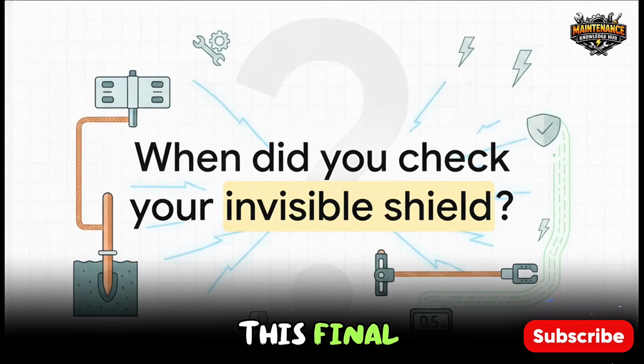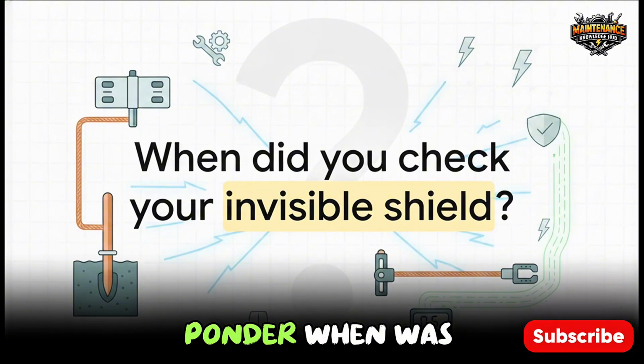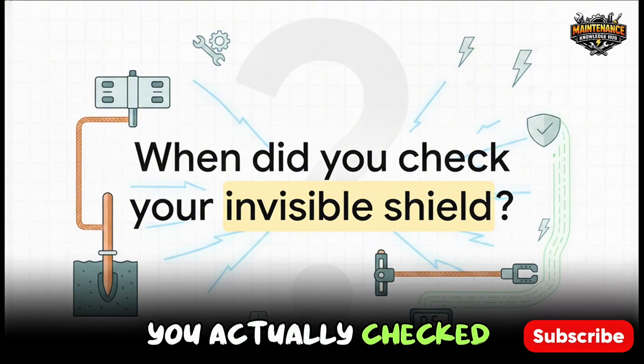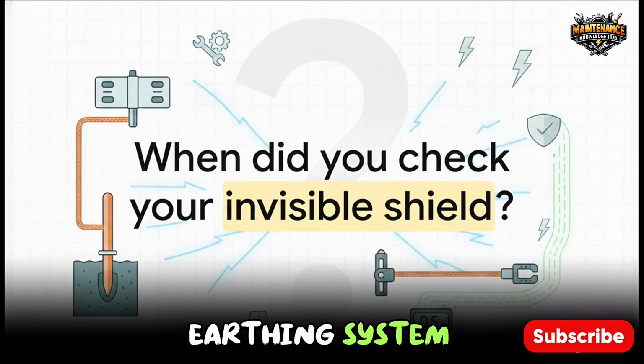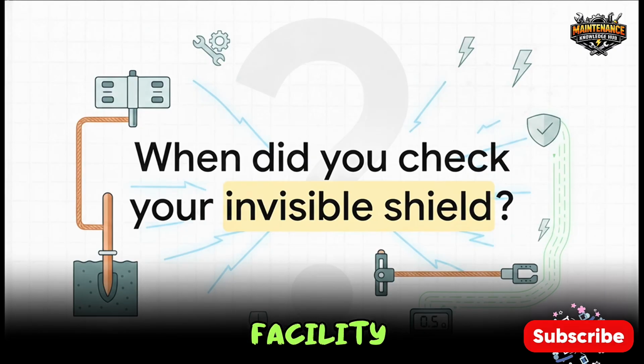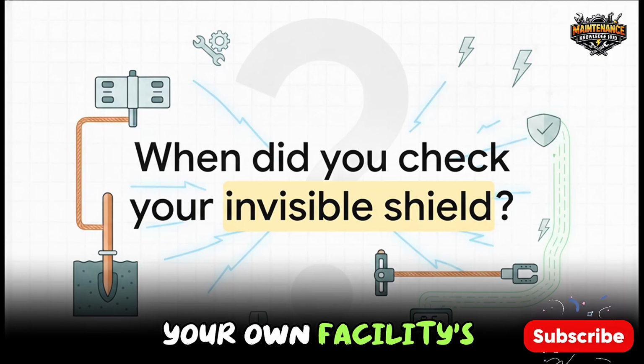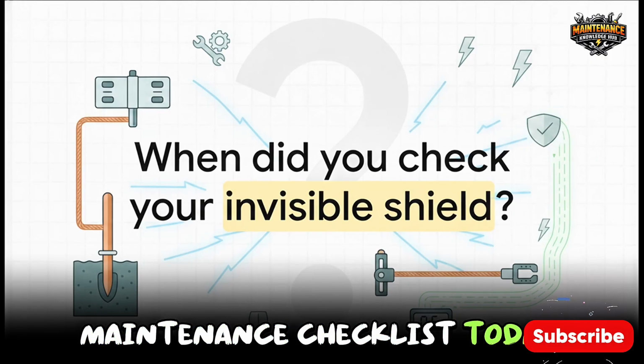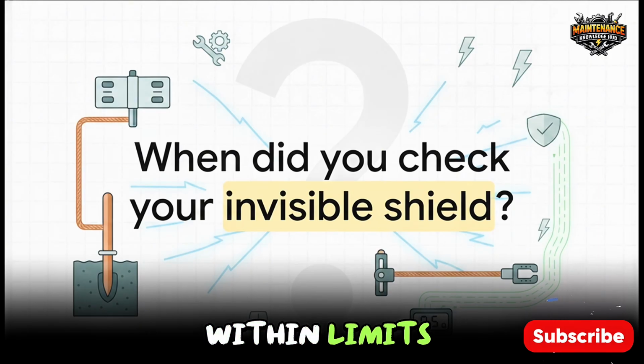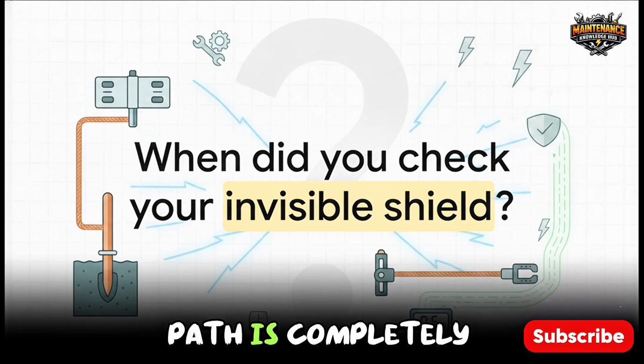So I'll leave you with this final, kind of provocative thought to ponder. When was the last time you actually checked your invisible shield? An earthing system only protects your personnel and your facility if that low-resistance path actually exists. So think about your own facility's preventative maintenance checklist today. Make sure your earth resistance is within limits, your connections are tight, and your safety path is completely clear.